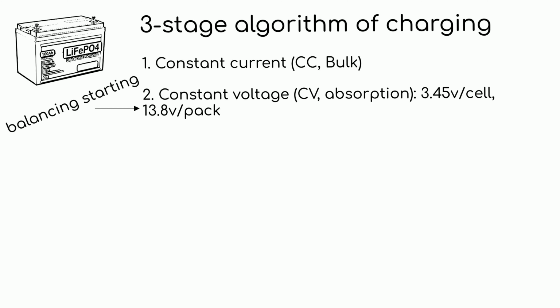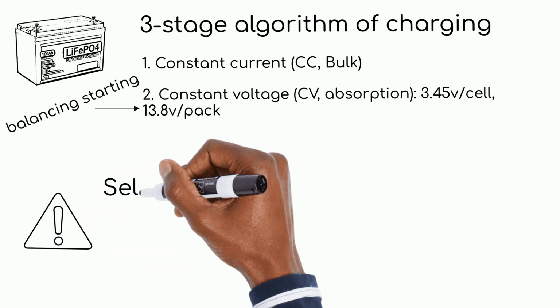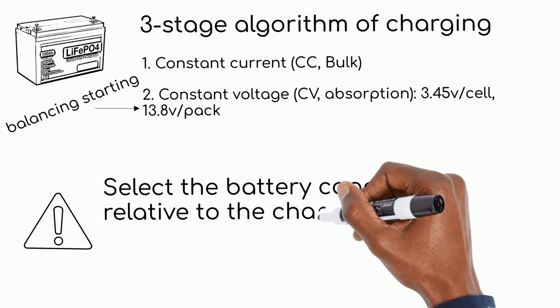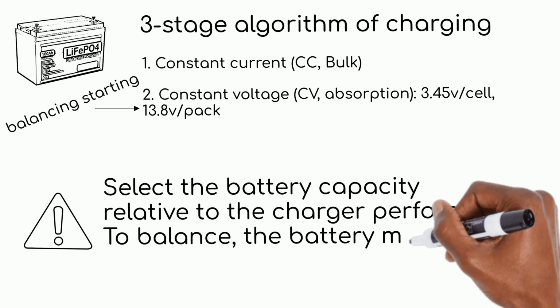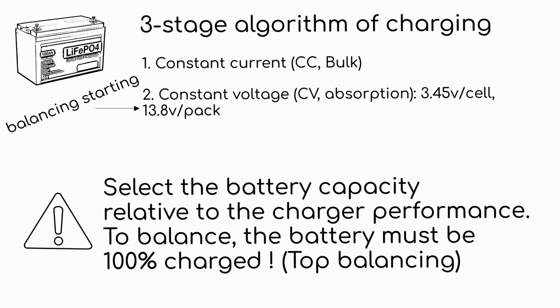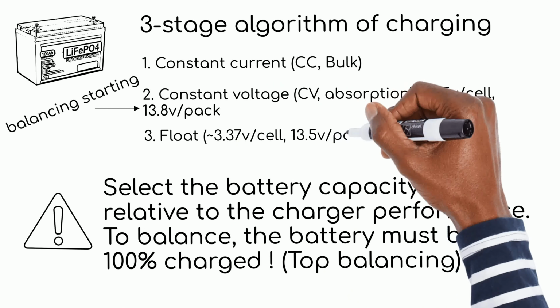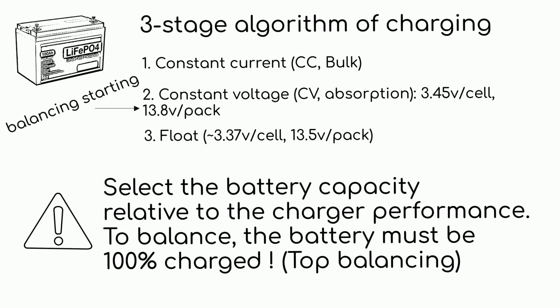Since effective balancing takes place at the end of the charging cycle, it is necessary to match the charging resource to the total battery capacity to ensure that the battery is fully charged at least occasionally. Float mode. Historically, this mode was added to chargers to compensate for the self-discharge of lead-acid batteries. To charge LFP batteries, we do not need this mode, but it is usually available in the charger settings. It's a good idea to set the float mode voltage a little lower than the rest voltage point. For example, 3.37 volts per cell or 13.48 volts per battery.